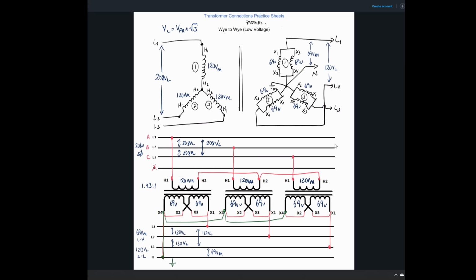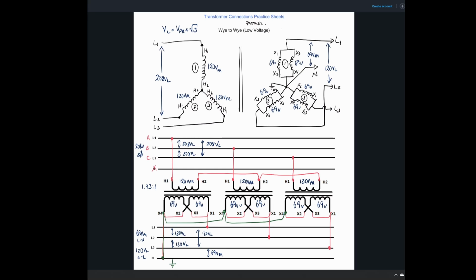Same configuration, Y to Y, but again, we're going to do the high voltage connection. And before I move on, there is something here that I can see that can cause confusion as to the way that I've done this. So I didn't make use of this neutral because in our shop, we don't have a neutral on our transformer stations. We just have 3-phase coming in. So for us, in order to create that Y, we're just going to tie our H2s together. But normally on either side of this transformer, this center point is often bonded to ground, both on the primary and the secondary. There's lots of discussion as to whether it's always bonded to ground on primary and secondary, whether it's just bonded on the secondary. But I can see that I may have caused some confusion here in that I didn't make use of that connection and I didn't show that being bonded to ground.